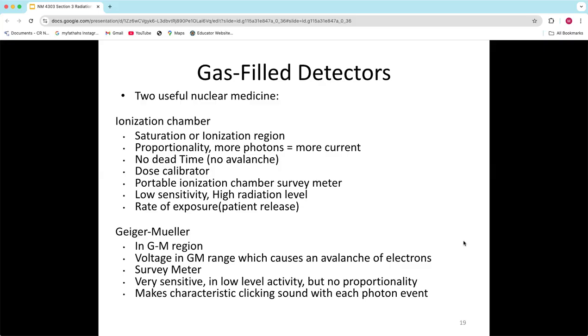Remember, an ionization chamber functions in that saturation or ionization region. It has proportionality, meaning more photons or more radiation will give you more current. There's no dead time, meaning it doesn't have that avalanche. We can sit on something and get a reading, measure our patients who have had iodine treatment and see where they're at, and it will just sit there and collect and collect what their dose is.